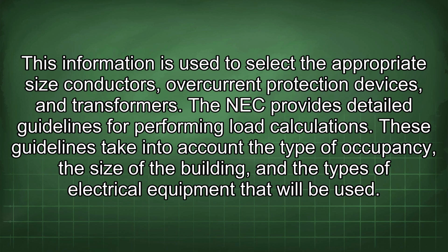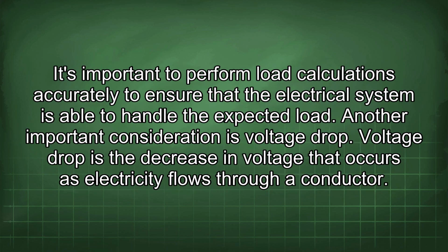The NEC provides detailed guidelines for performing load calculations. These guidelines take into account the type of occupancy, the size of the building, and the types of electrical equipment that will be used. It's important to perform load calculations accurately to ensure that the electrical system is able to handle the expected load. Another important consideration is voltage drop.